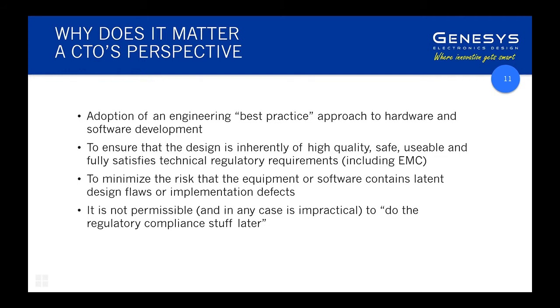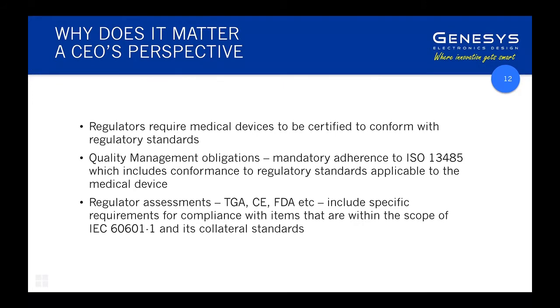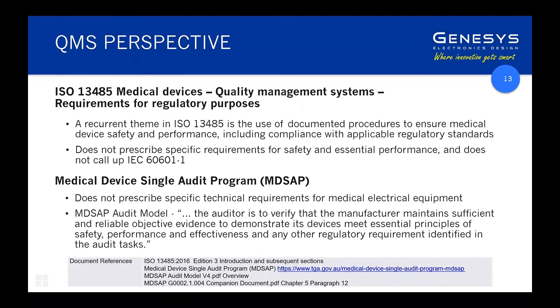The CEO will want to ensure their device can be legally marketed in the jurisdictions where they want to sell it. To do that, it's obligatory to comply with ISO 13485, which calls up a requirement to comply with applicable regulatory standards. 13485 doesn't specifically call up 60601-1, but you will find 60601-1 applies in some form or other in all jurisdictions you're likely to want to sell your product in. So you have no option in this matter if you want to sell your product legally.